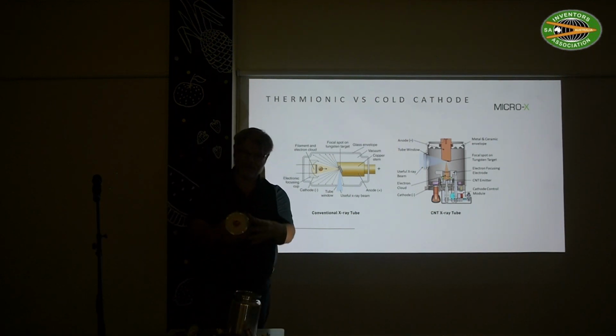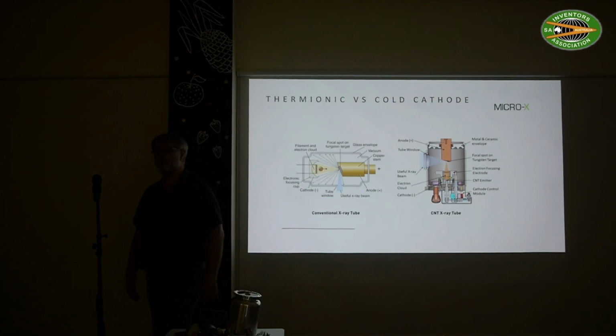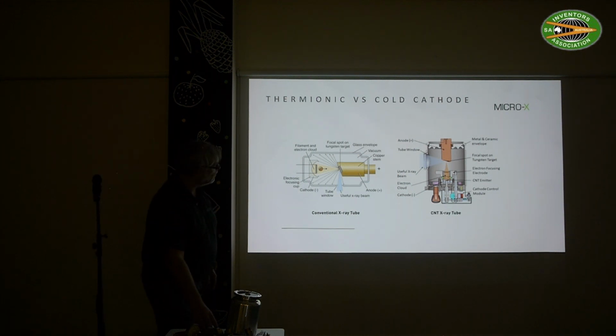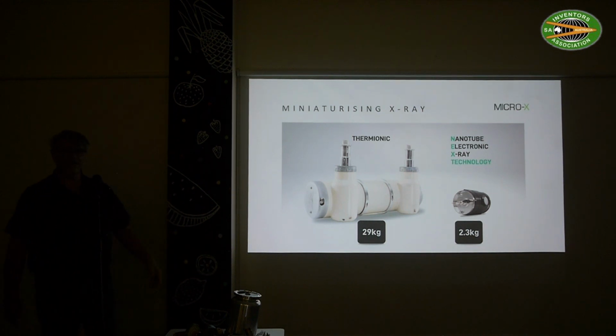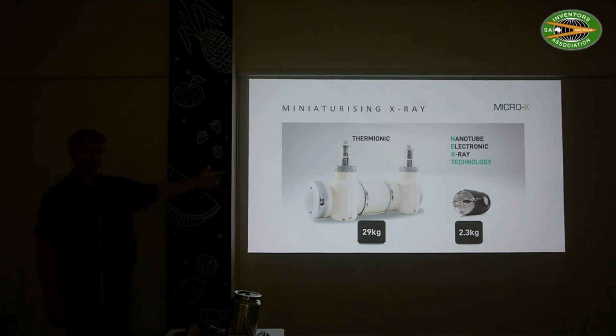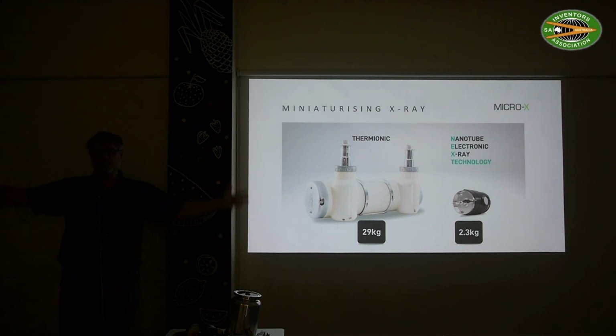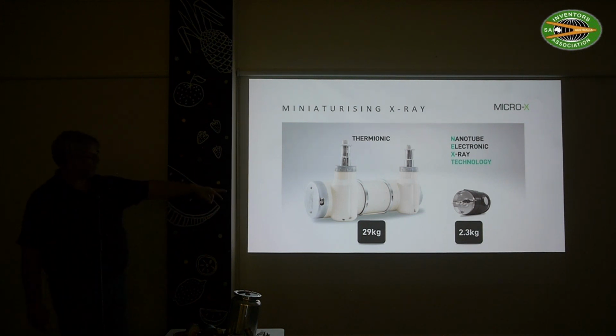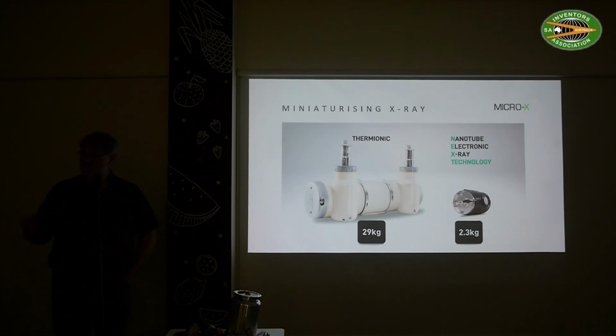So as you see it, this is essentially the full X-ray thing, complete. We don't have to cool it any further, which means the whole thing is a lot more compact. We're tenfold lighter than classic X-ray tubes, comparing X-ray tubes of comparable capacity in terms of how much X-ray they can produce. Because you get small ones for dentistry, and really big ones for CT machines. But these are comparable, and the classic one is 29 kilos and we are at 2.3 kilos. So that's a sort of level comparison.